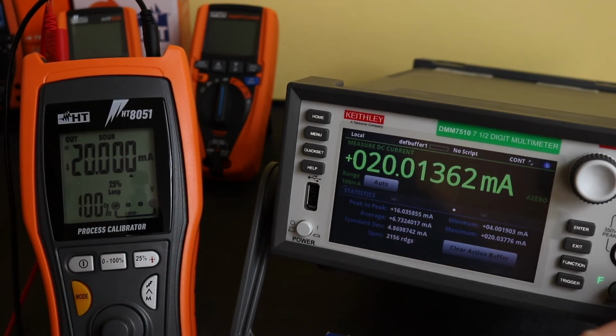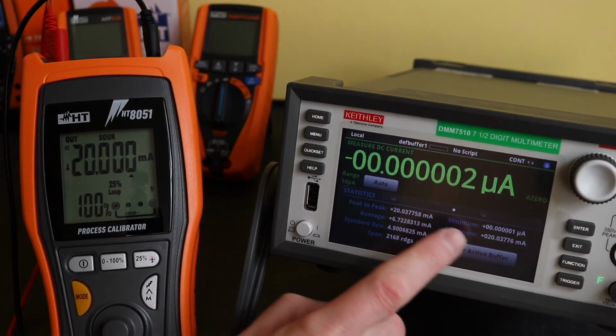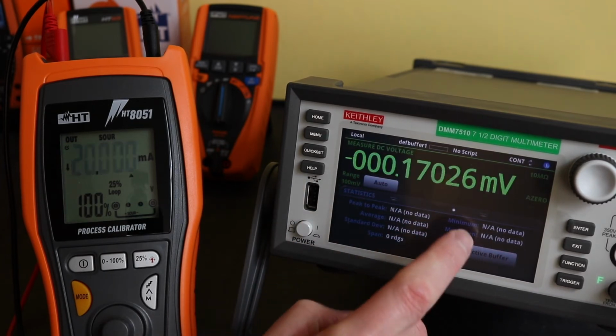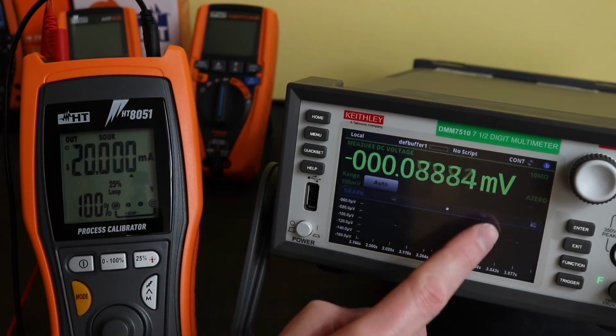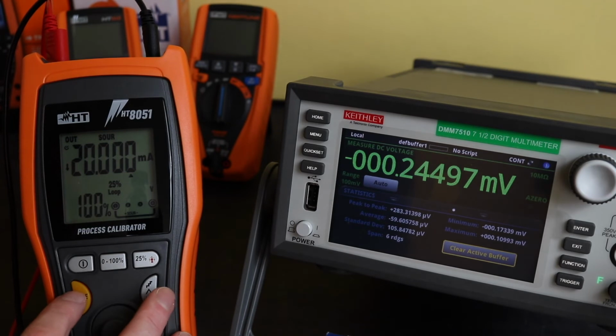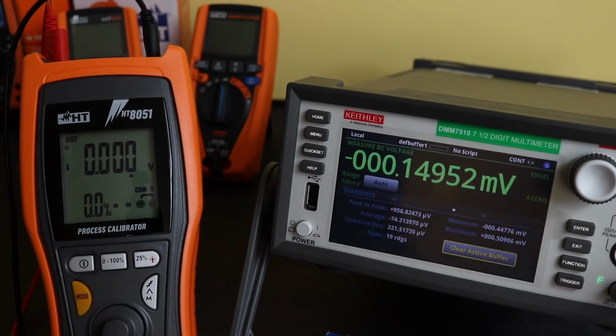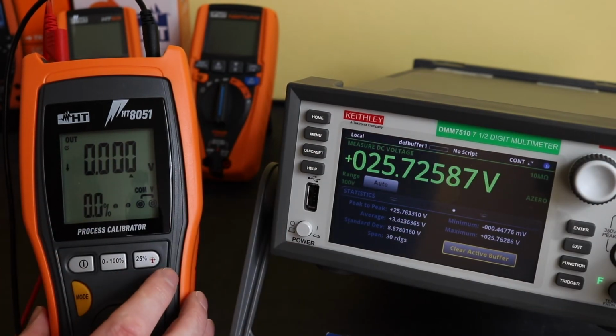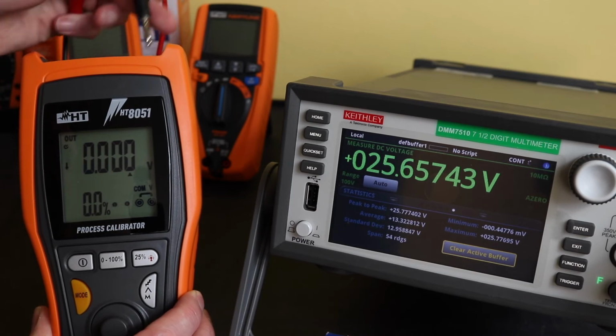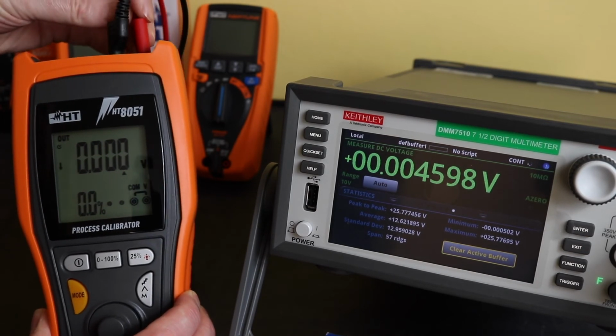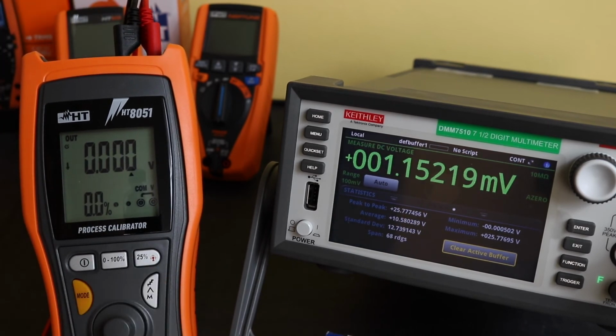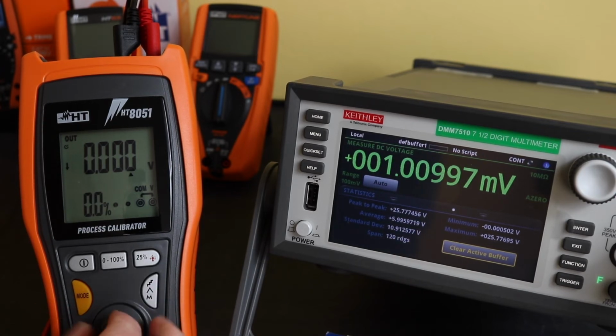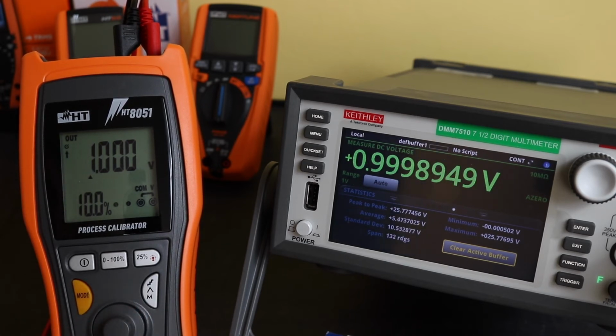We'll just change mode and we'll change over to voltage. And there we are on output volts there. So again we're on 0%. And then we need to change our connections at the top here as well. That's one disadvantage to this instrument. There's quite a bit of changing around of connections. We are on 0 and showing 1.16 millivolts. So what we'll just do is change this up to 1 volt.